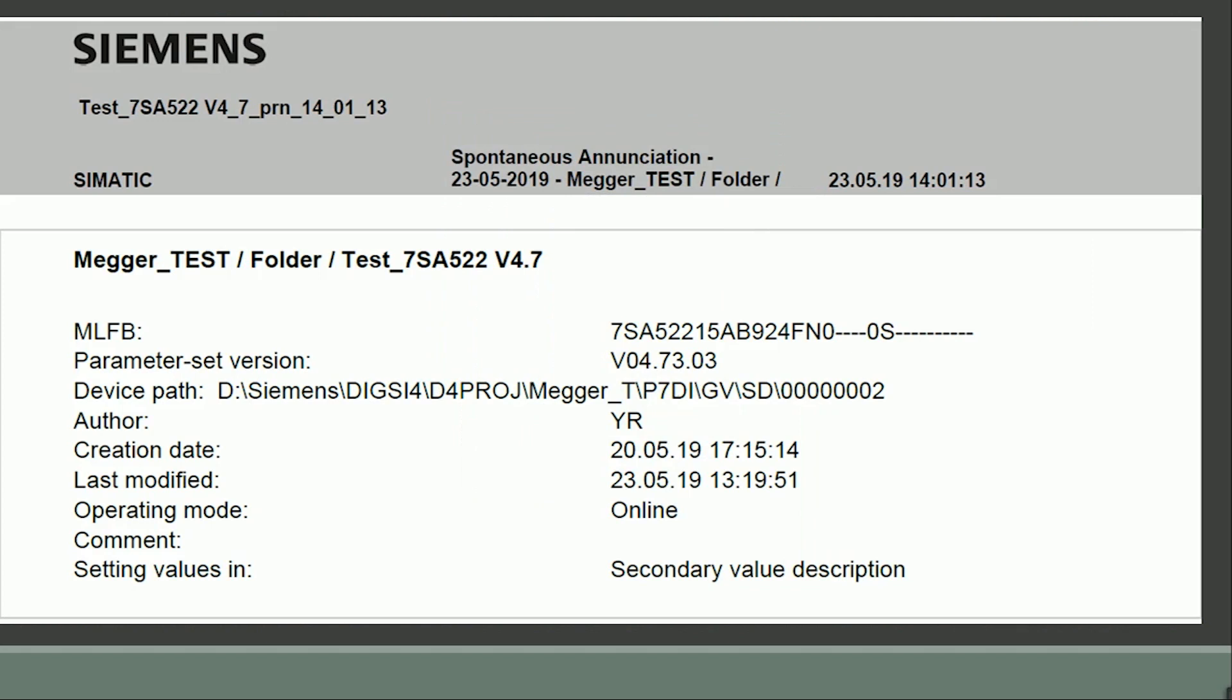Now let us analyze the event record. Using Siemens DIGSI software the event record is downloaded. The spontaneous event list shows the sequence of auto recloser function lockout state.